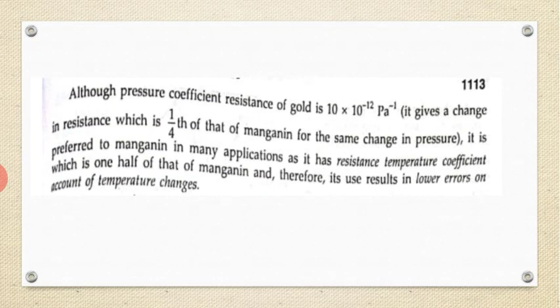The pressure coefficient of resistance of gold is given here as 10 into 10 raised to minus 12. It gives a change in resistance which is 1/4 of that of manganin for the same change in pressure. Hence it is preferred to manganin in many applications. Also its resistance temperature coefficient is lower than that of manganin, and therefore it results in lower error on account of temperature changes. So this is information related to the wire which is used here.